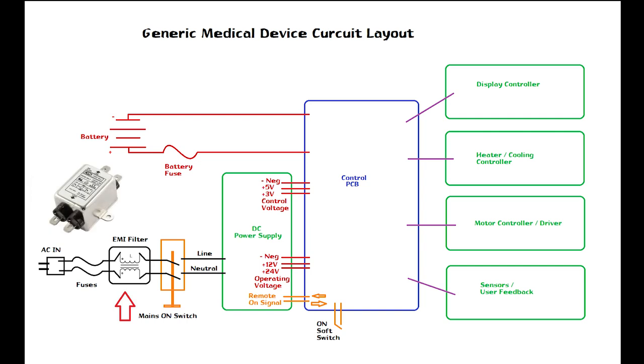Following the EMI filter, that's where we go into a mains on-off power switch. Now not all devices have a mains power switch. Sometimes they just have a soft switch.